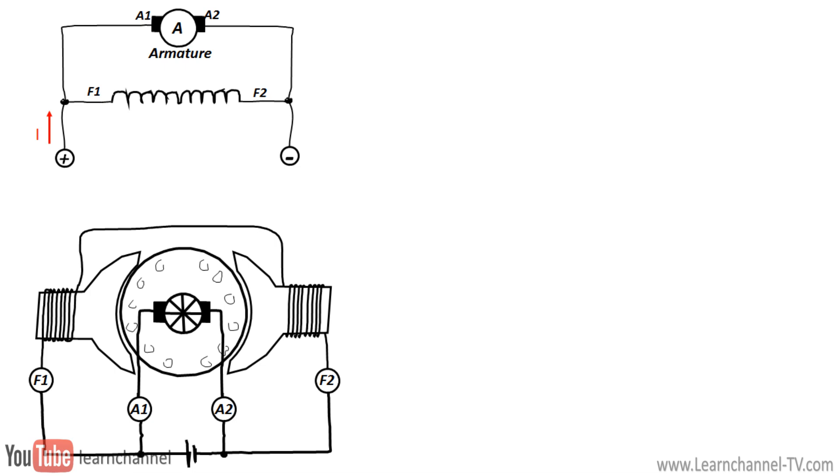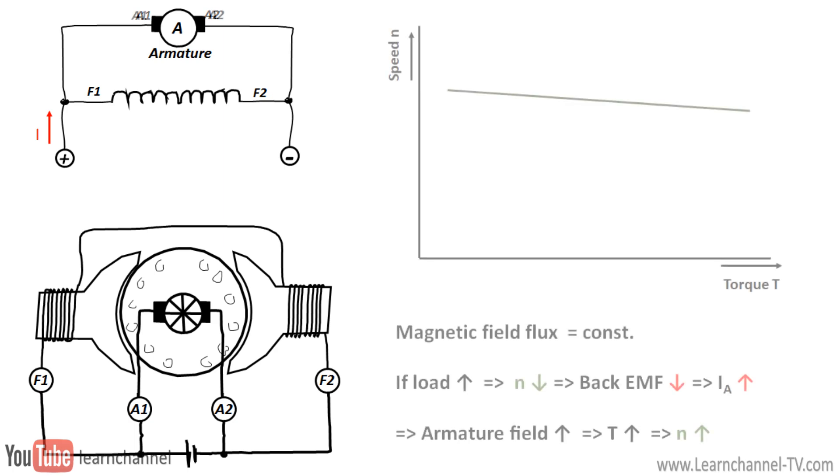As we know, the rotating armature produces a back EMF, which opposes the armature voltage and therefore reduces the armature current. If the load on the motor increases, the armature rotation slows, and thus the back EMF also is reduced, since back EMF is proportional to speed. The decrease in back EMF results in an increase in armature current. Since torque is proportional to armature current, torque must also increase.